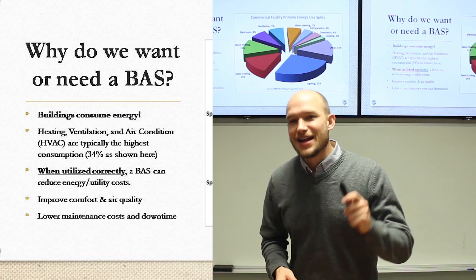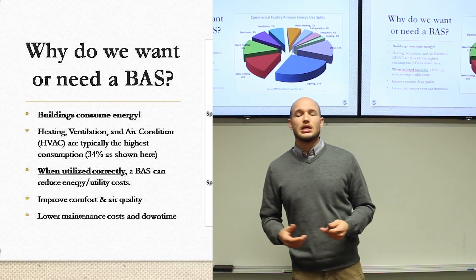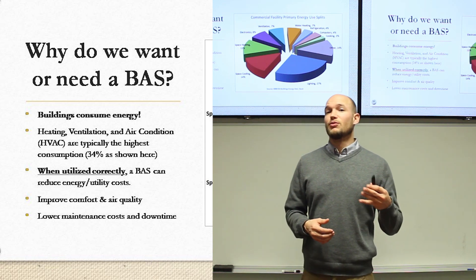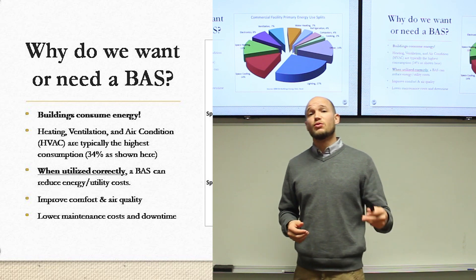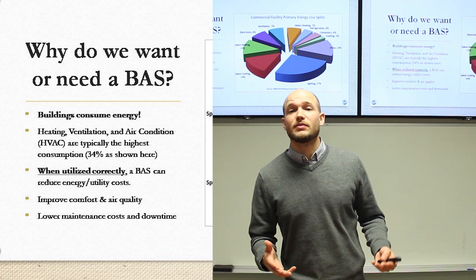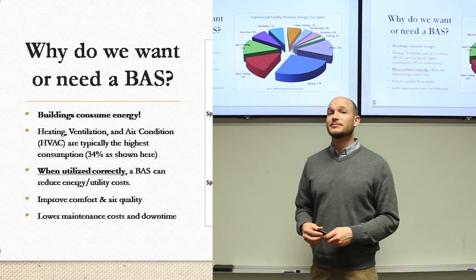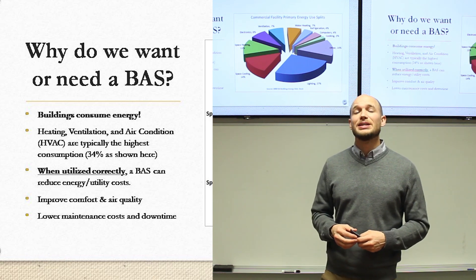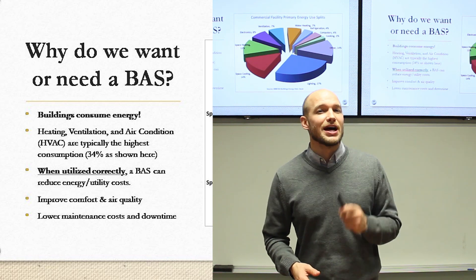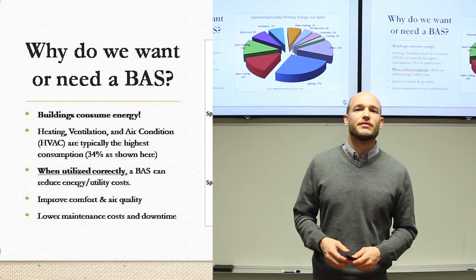When utilized correctly — notice that's underlined and bold — because when it's not utilized correctly, these systems can actually cost you more money. For example, a user goes in and overrides a room or even the whole building to 72 degrees heating, forgets about it, goes home at night, and the system runs day and night at 72 degrees heating for days, weeks, even months before someone notices. Those overrides can definitely get tricky.